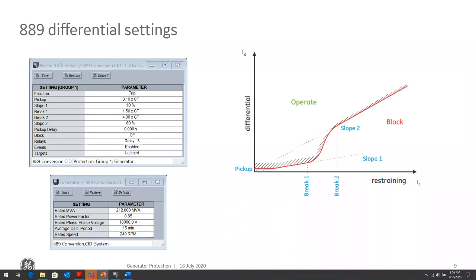So the question was, why are we not using 50 instantaneous overcurrent protection in high capacity generators? So a couple of things with that. Usually, as I mentioned, for example, let's talk about phase faults. We don't want to set a 50 instantaneous overcurrent because for faults out in our system, that 50 instantaneous will see those conditions. So we might erroneously overtrip the generator for faults outside of the system. So we want to coordinate for the faults outside of the system.